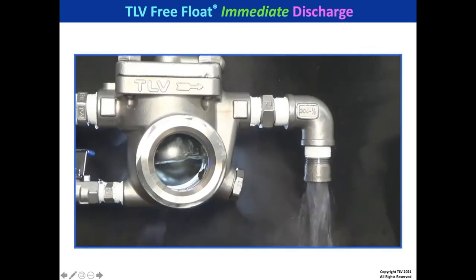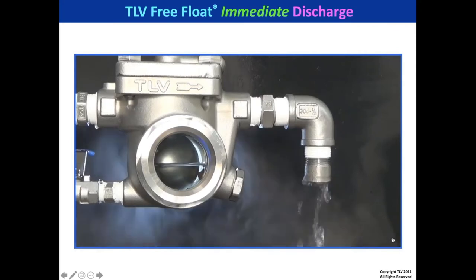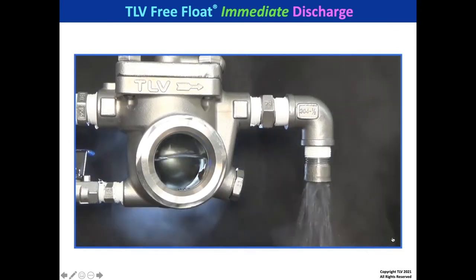Here we see a video of a float trap in operation. Notice that even though the load is changing, a seal is maintained over the orifice and steam stays in the top of the body. It shows how quickly it synchronizes with the condensing of the steam in the reboiler, and that's why I prefer a float trap.